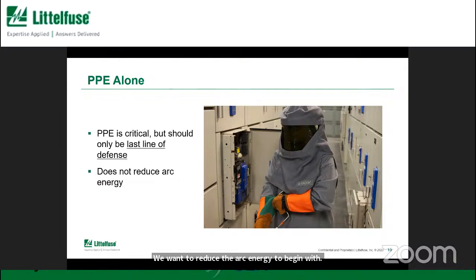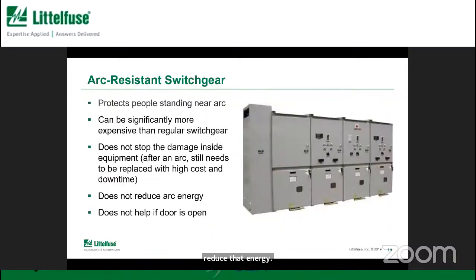So the suit itself, although it might protect you in the case there is an arc flash, we don't want the full arc flash energy. We want to reduce that energy. Another thing that is talked about a lot is arc resistant switchgear. So this is equipment that is designed so that if there is an arc flash, it is contained inside the equipment. It's built strong enough so the doors do not break open, and all the energy is redirected out. And usually there are flaps on the top, or there might be a plenum that goes outside the building and directs the energy out.